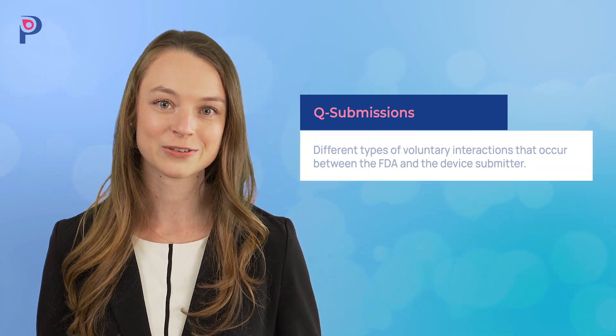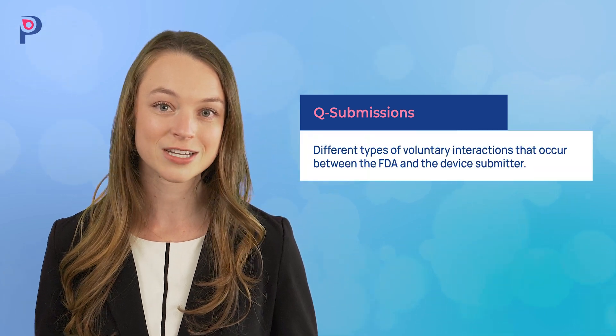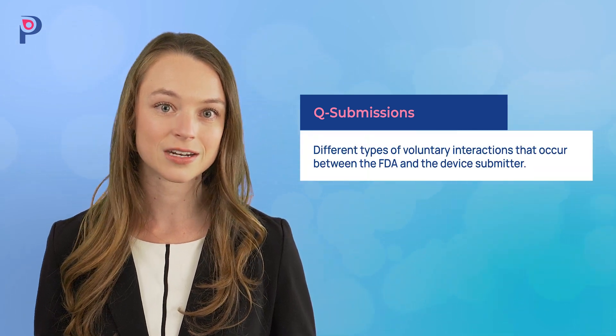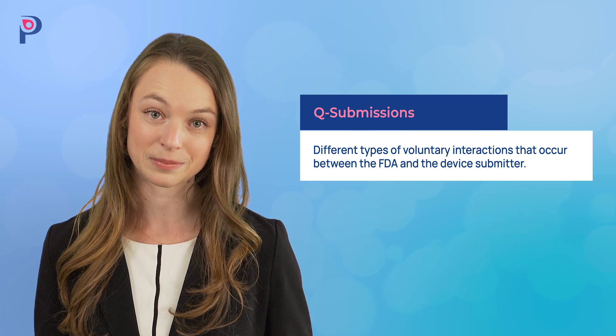Q-Submissions are different types of voluntary interactions that occur between the FDA and a device submitter. These interactions can be requested for feedback or meetings regarding medical device submissions. Q-Subs are useful because they can afford valuable opportunities to share information with the FDA or gain input from outside of the pre-market submission process.